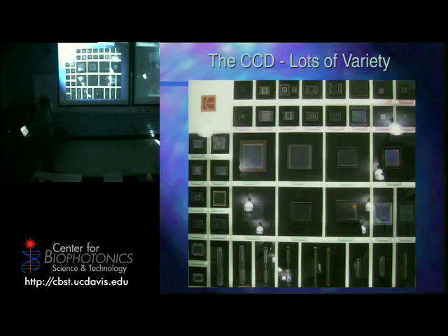Okay? Now, there's also CCDs that look like this, just a single linear strip. And actually, in the spectrophotometer that you guys are going to be using, that's the kind of CCD that's in there. It's a linear strip. It's basically 4,096 little photodiodes all in a line. Okay? Just running straight down. So I don't need a camera type sensor in there. I don't need a two-dimensional sensor. I just need the one strip. So these are more like your fancy cameras. Okay?